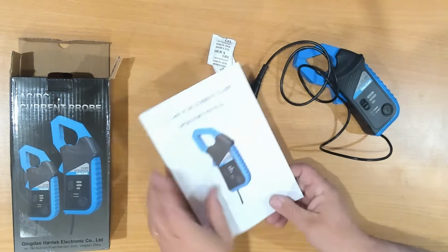It does not come with the battery. Battery life is typically 100 hours with a carbon-zinc. I've actually got an alkaline in there. Dimensions, it lists as 195mm by 70mm by 33mm and weighs in at 250 grams. So this has not got a lot of controls on it, so your zero adjusters are down here, and you can turn it on 10 millivolt per amp range and push it all the way up for 1 millivolt per amp. There's the range on it.